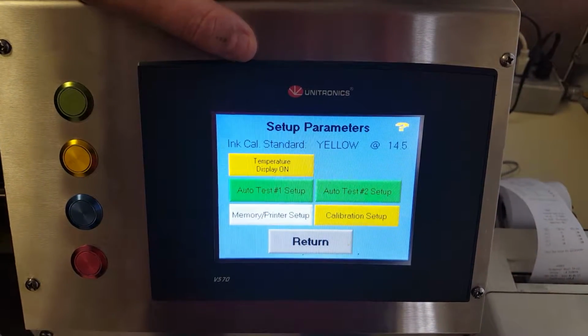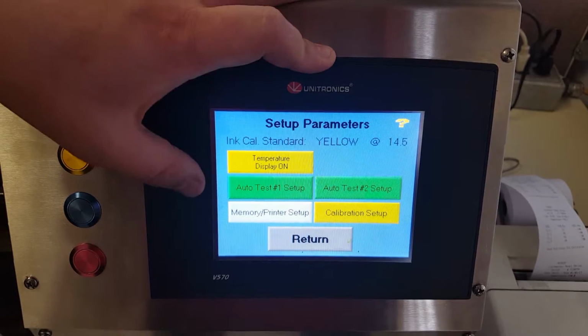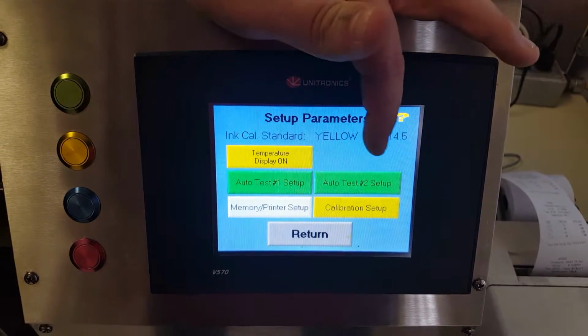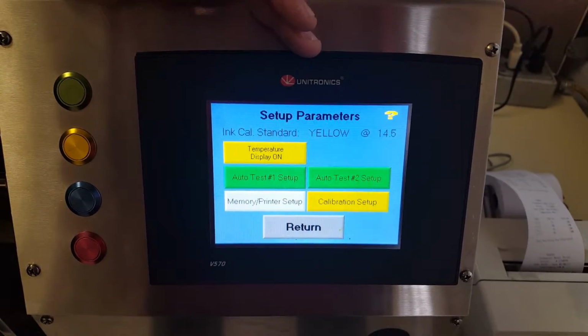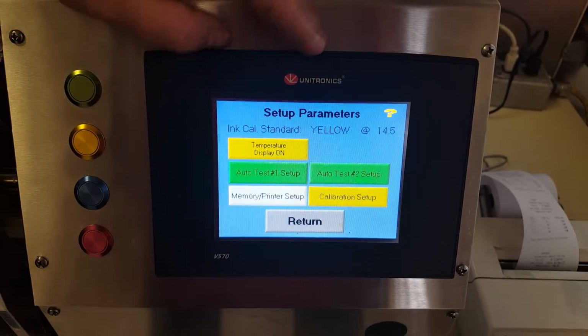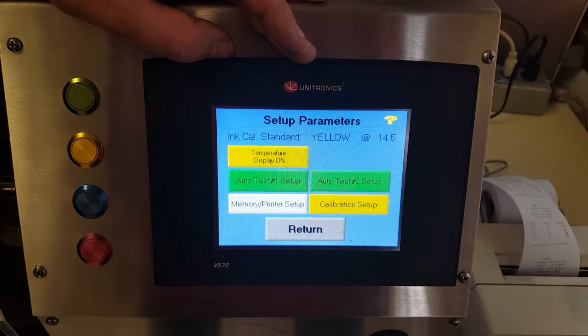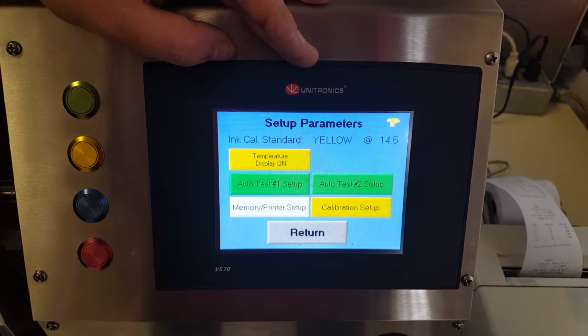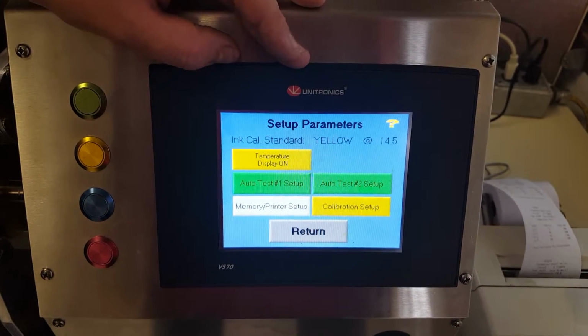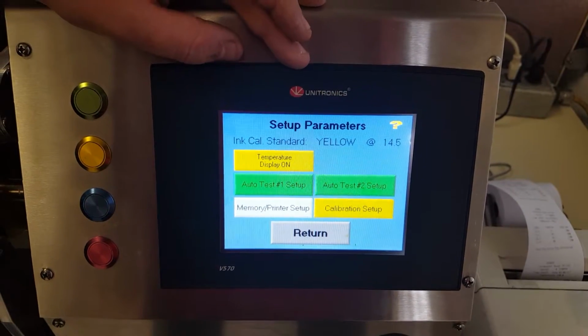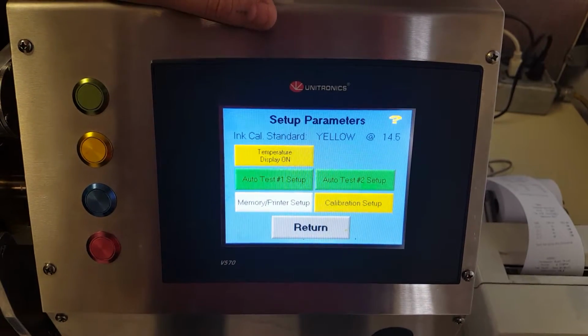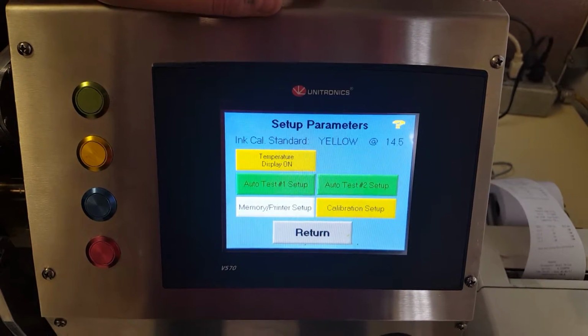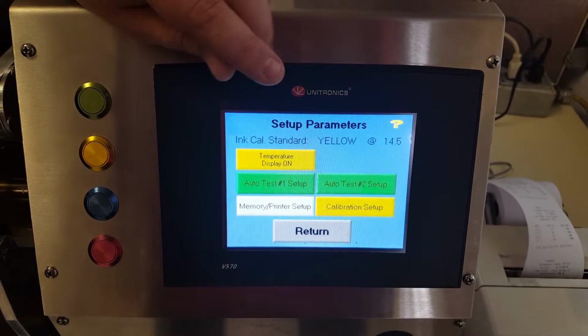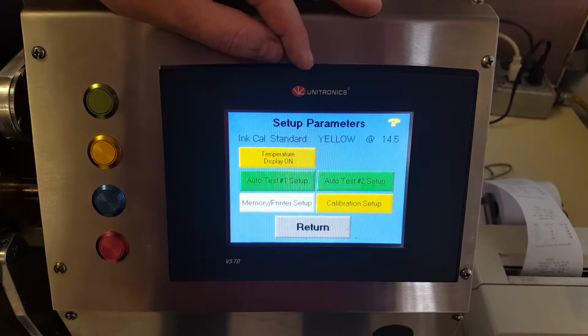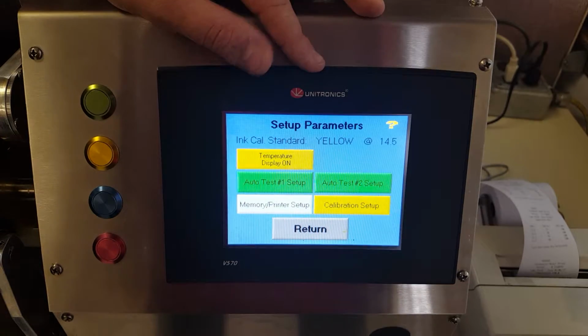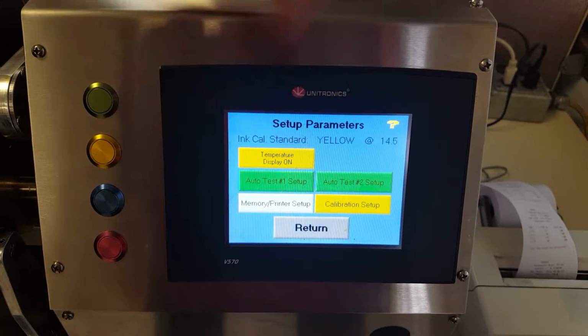Very simple. Now beneath that we have two automatic test setup screens. The reason we have two separate setup screens is that people often run a test at high speed for a long period of time, or at low speed for a short period of time, or with different calibration standards. This lets us pre-program the parameters of each test individually, so you can select between one or the other before running the test without readjusting the settings each time, if you choose.